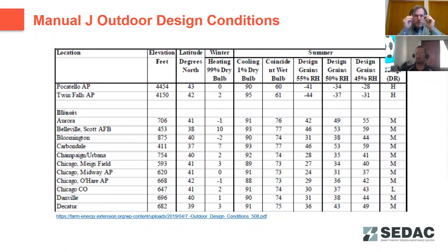What we're sizing for with the Manual J is that 95, in this case 99% condition for cooling. We're not designing for the absolute hottest day of the year. We're designing for what's typical, and then the system should run continuously at that design condition and beyond if it gets warmer, and still be able to maintain comfort, although your house may warm up slightly. But it's such a rare event that you don't want to over design your system to cover those very rare events, and then have for the rest of the year an inefficient system.